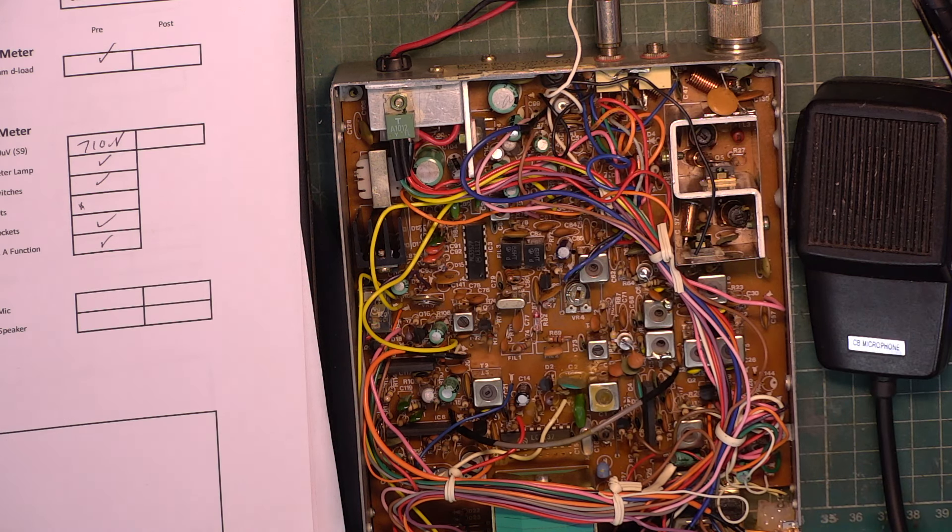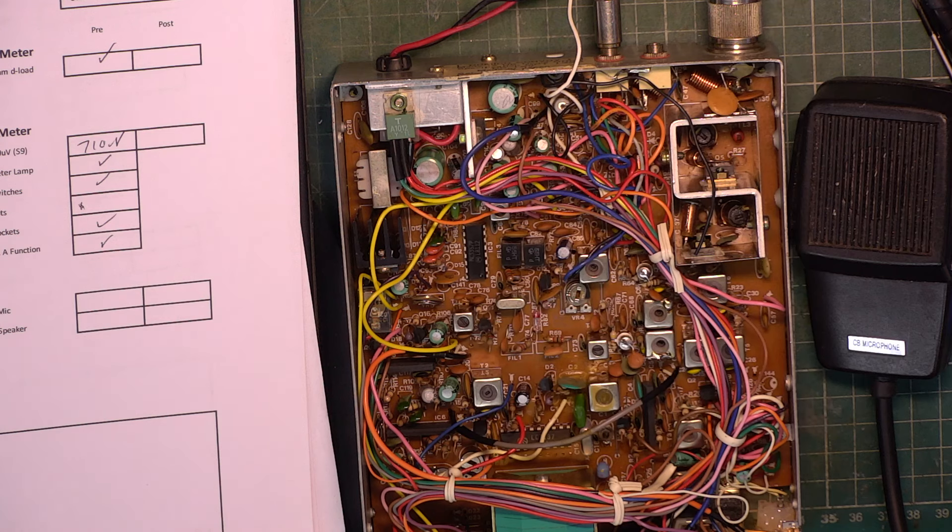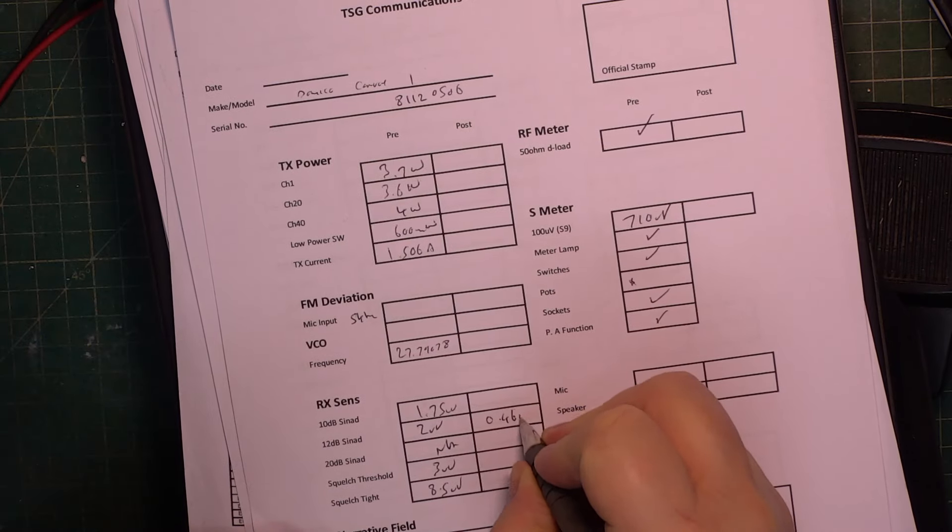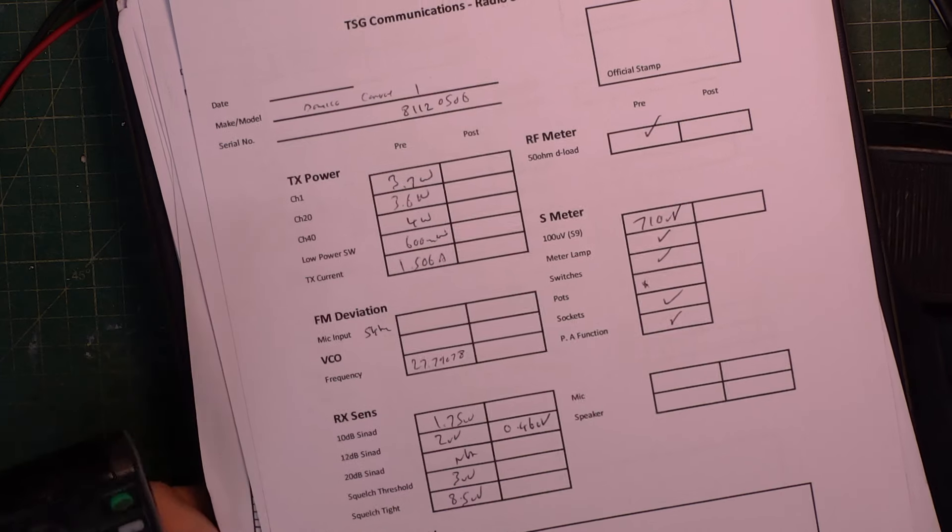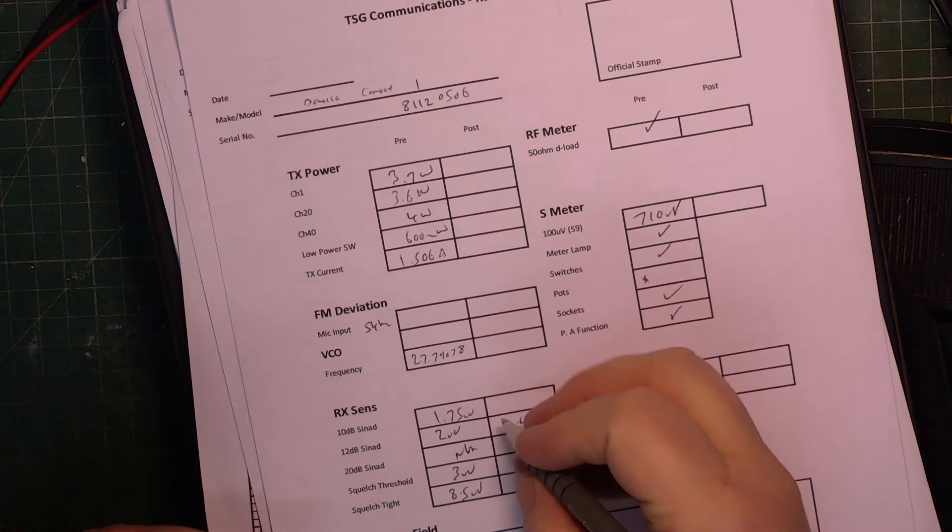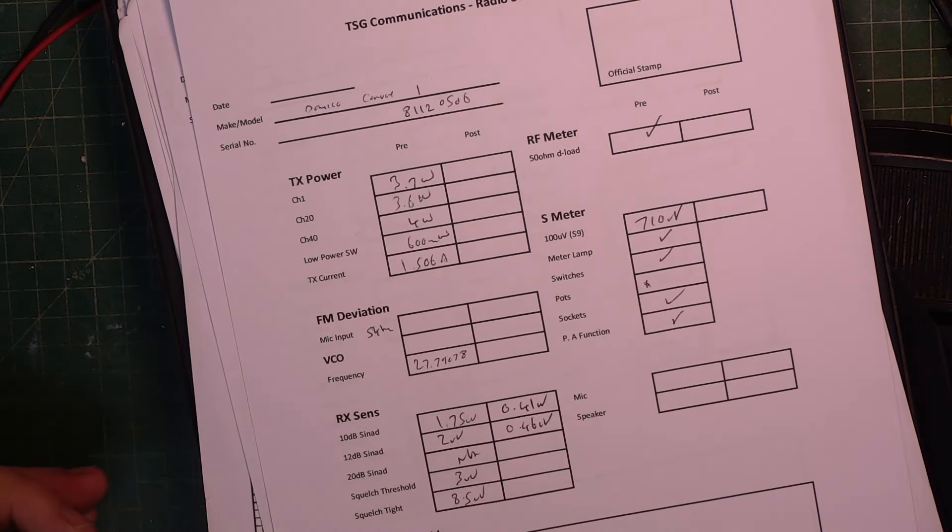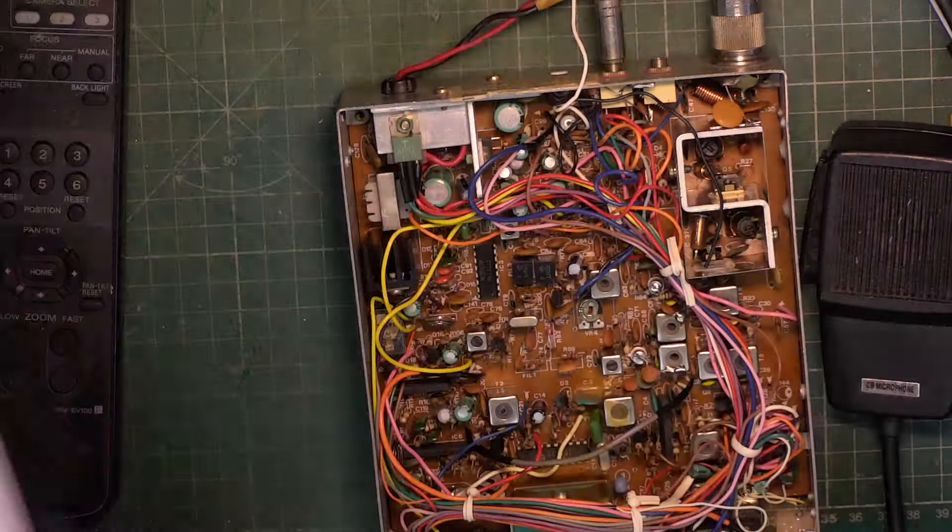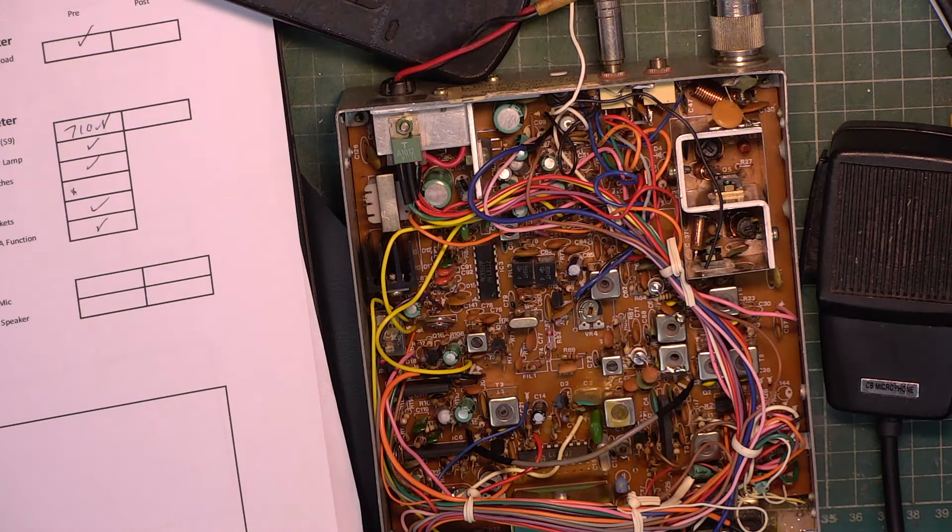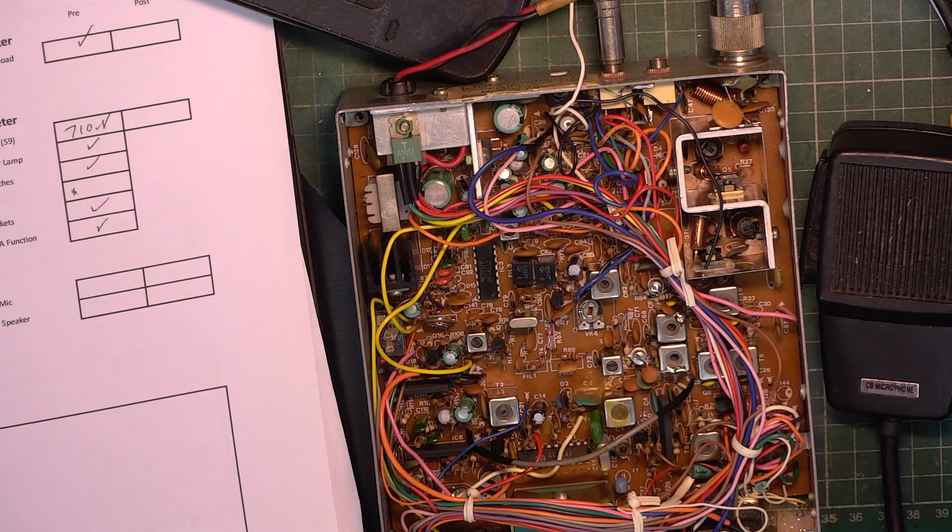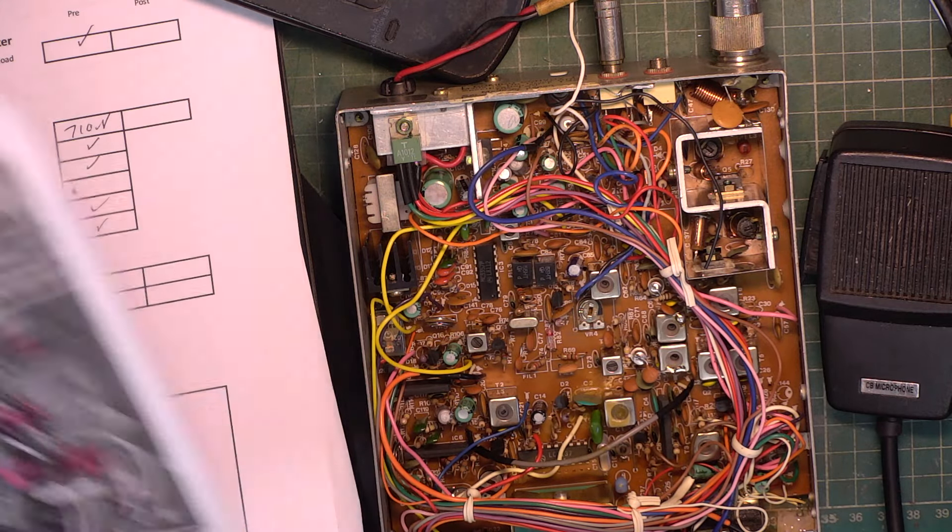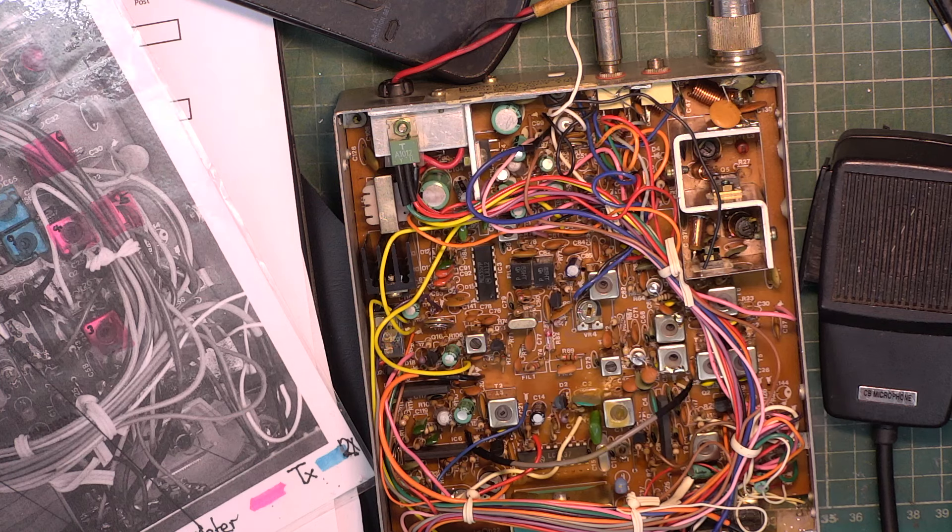Okay, so let's read off what we've got. We've now got sensitivity at 0.46 microvolts and we've got 10 dB. 0.41. And we've got 20 dB, if it ever does it. No, it's never going to do it. Now that's interesting because, that's usually sounds like the detector's not in the right position.